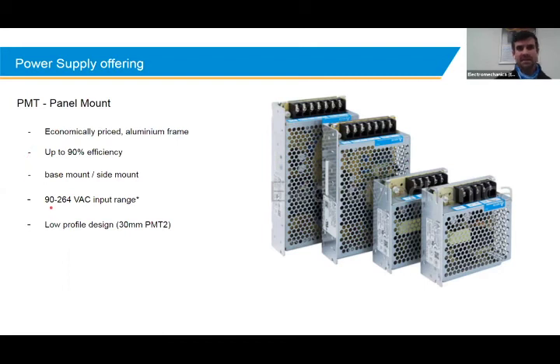Quite a wide range from 90 to 264 volts AC. Some of the panel mount power supplies would have a little switch on the bottom to change over from, say, 90 to 130 volts or 180 to 264 volts. So depending on what country you're in, America or South Africa, you would just flick the little switch on the bottom of that PMT just to change that input voltage. So it's not a true entire range like it's illustrated here, but you'll note that some of them would have a little dip switch to change their voltage input. If you look on page B58, that's specified by the little red star, that those power supplies in particular would have the little dip switch at the back.